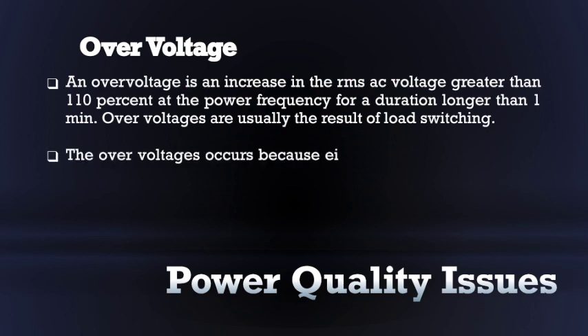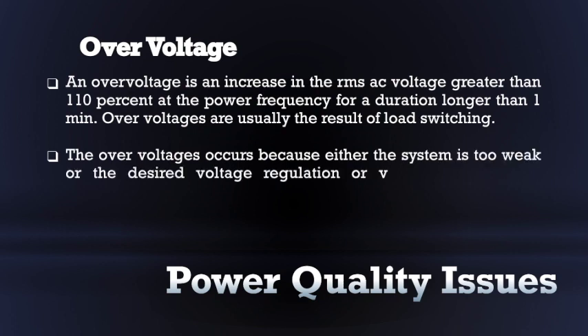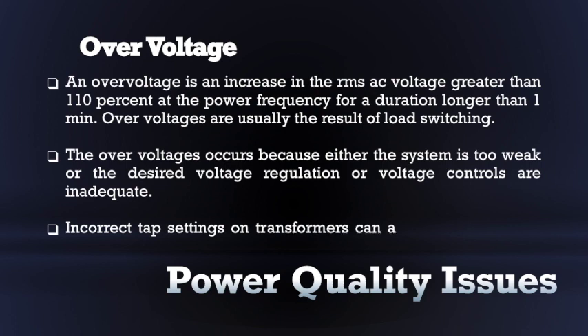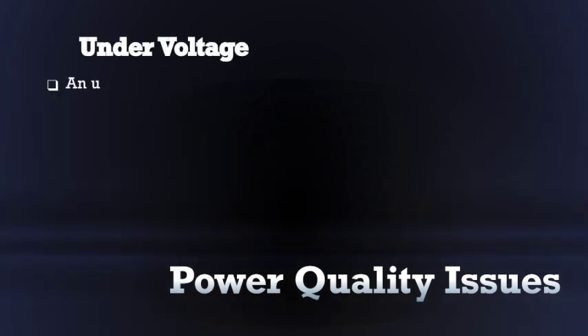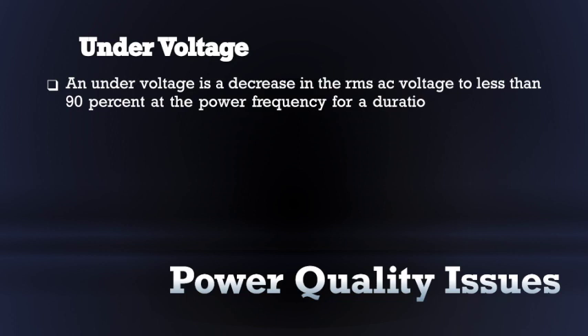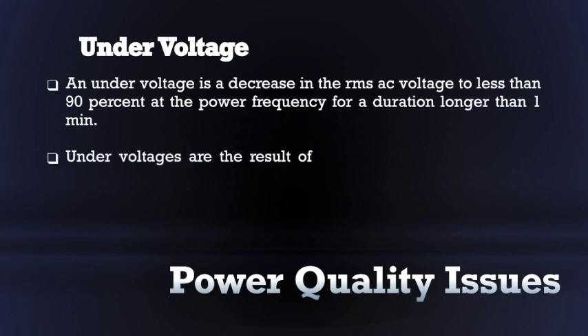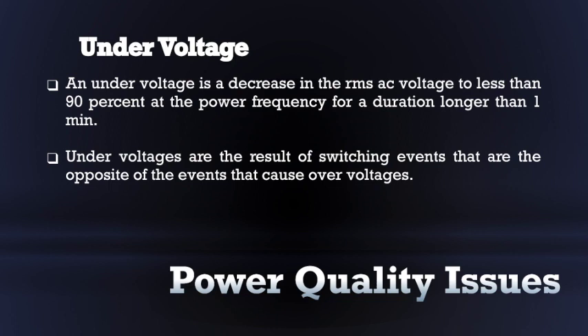Overvoltages are usually the result of load switching, for example, switching off a large load or energizing a capacitor bank. This condition occurs because either the system is too weak for the desired voltage regulation or the voltage control methods are inadequate. For example, incorrect tap settings on transformers can also result in system overvoltages. An undervoltage is a decrease in the RMS AC voltage to less than 90% at the power frequency for a duration longer than 1 minute. Undervoltages are due to the switching events that are opposite to those that cause overvoltages. A load switching on or a capacitor bank switching off can cause an undervoltage.